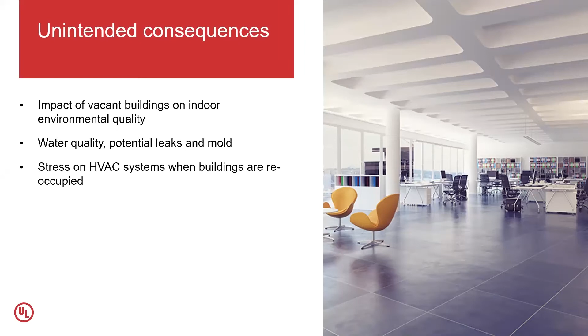I tell people all the time, a fan or a pump is the best colleague you'll ever have. If it runs on a pressure set point, it will run on that set point until it breaks, doing everything it can to reach it. So really understanding your building or facility and how it interacts with the greater environment is key - how vacant spaces can have multiple compounding effects on the indoor environment in the long run, and on the mechanical systems too.